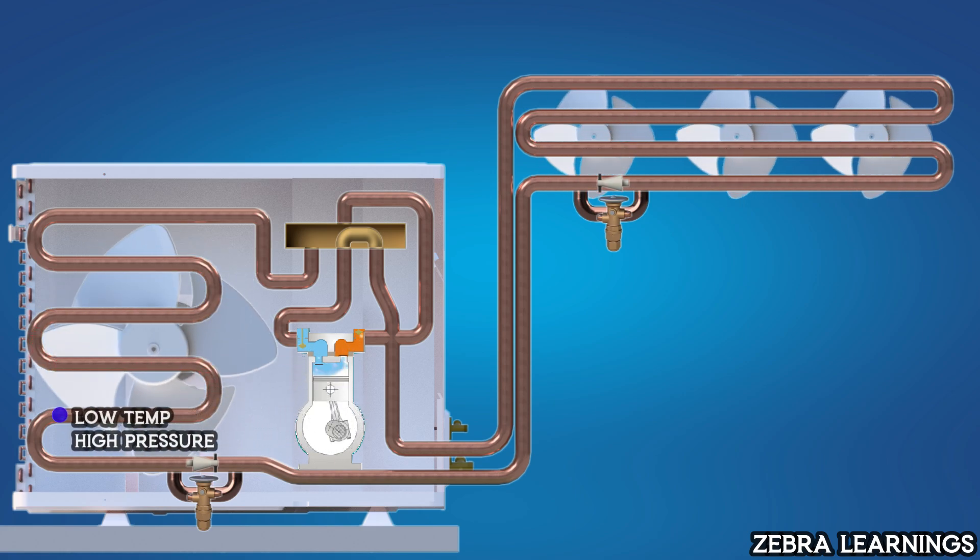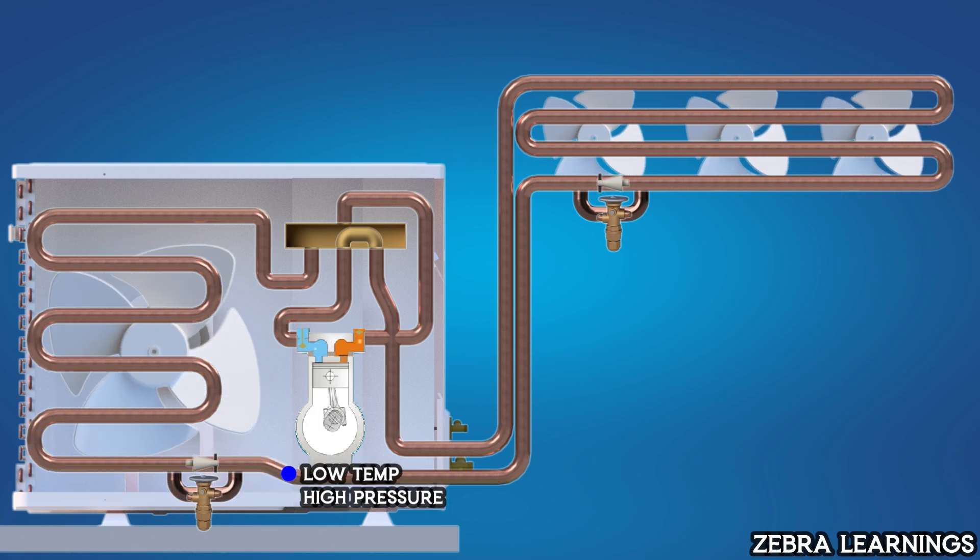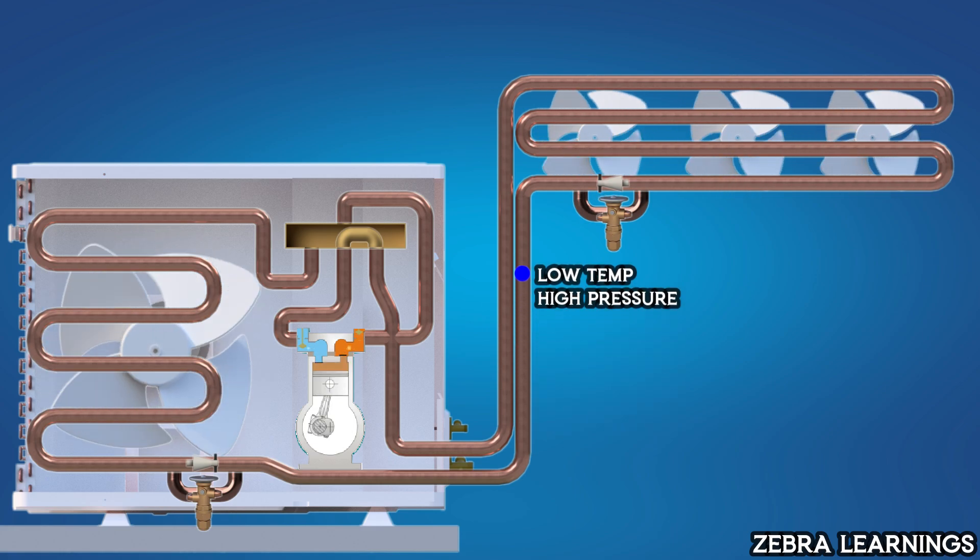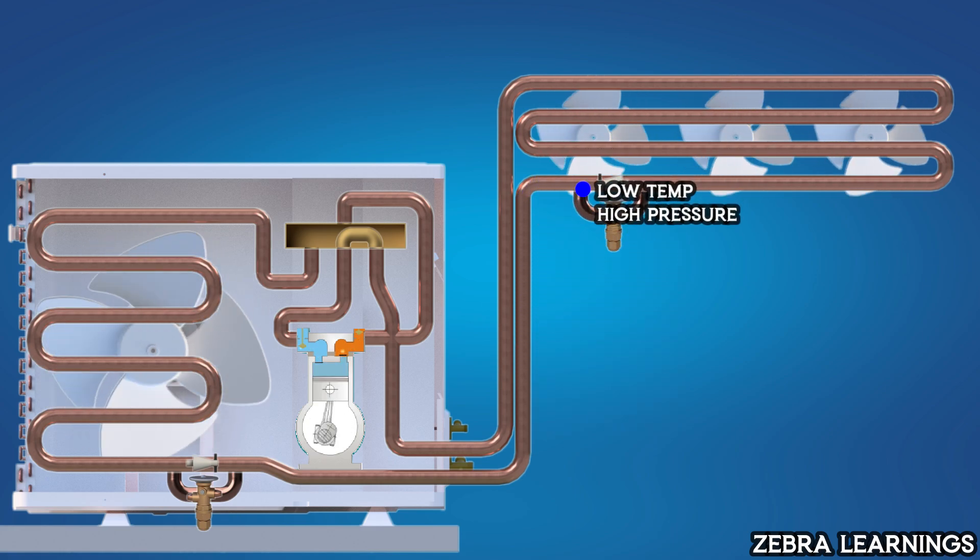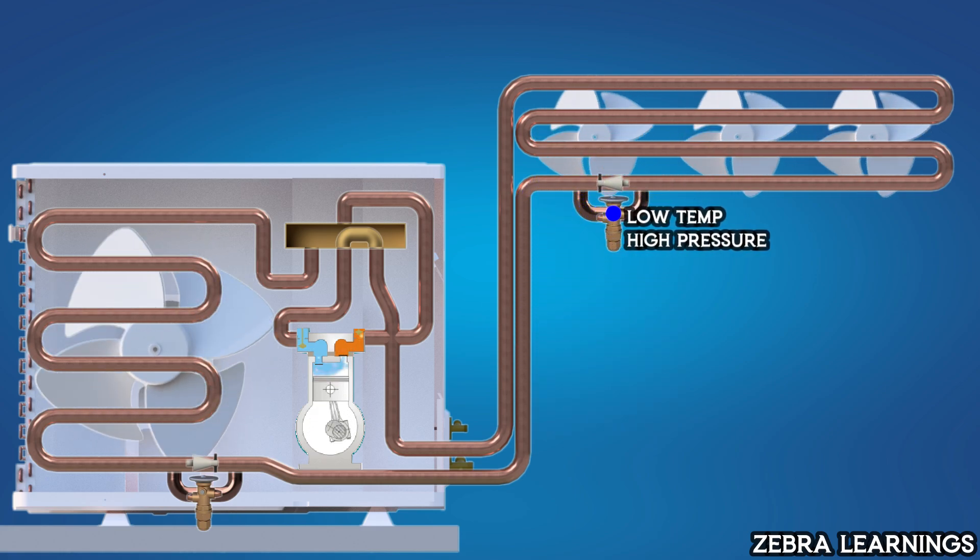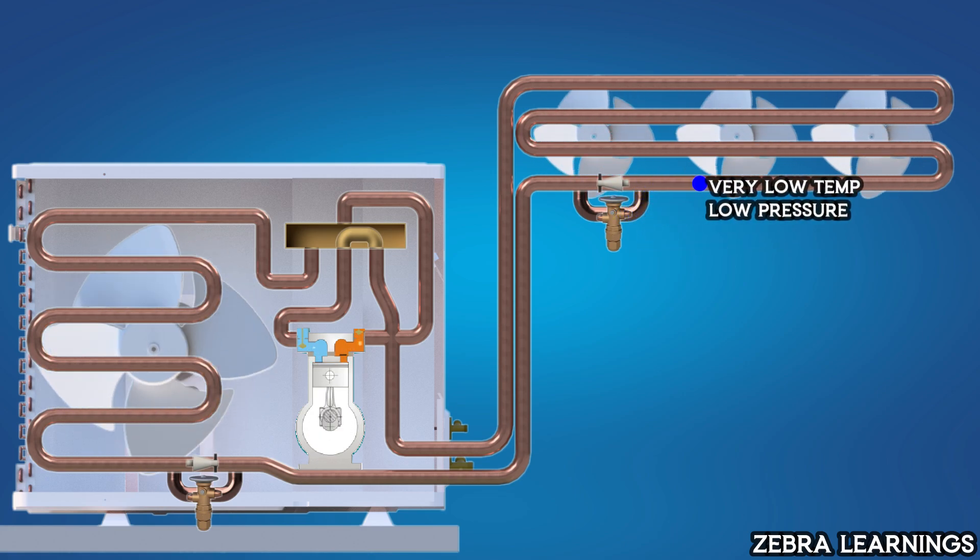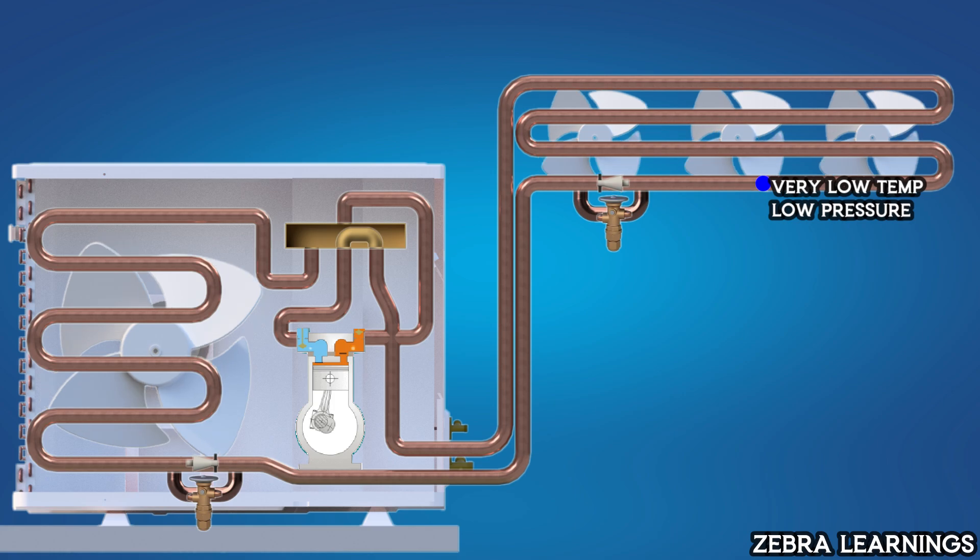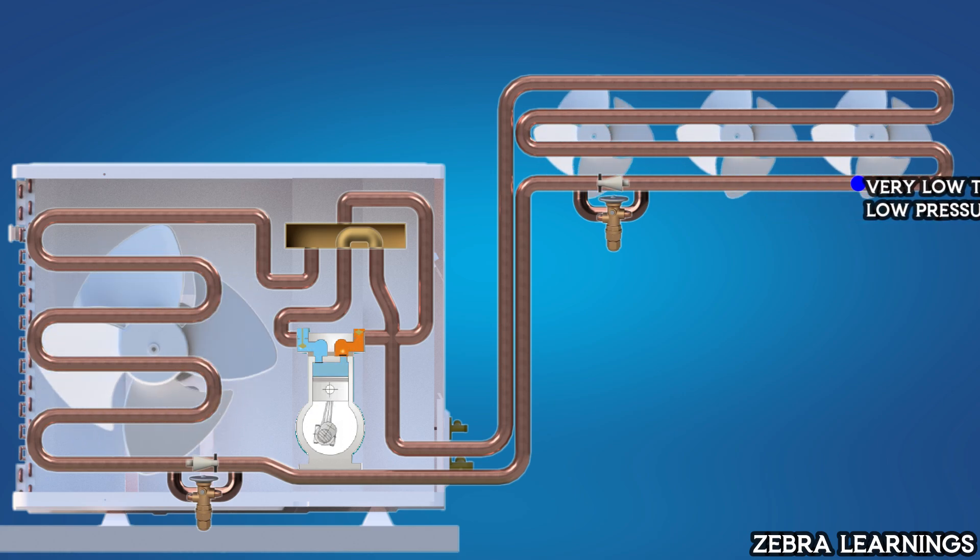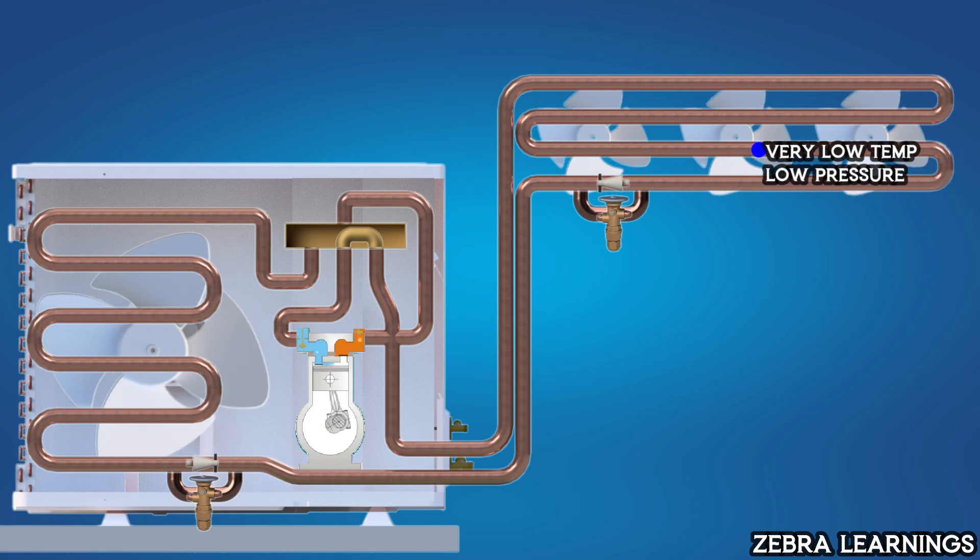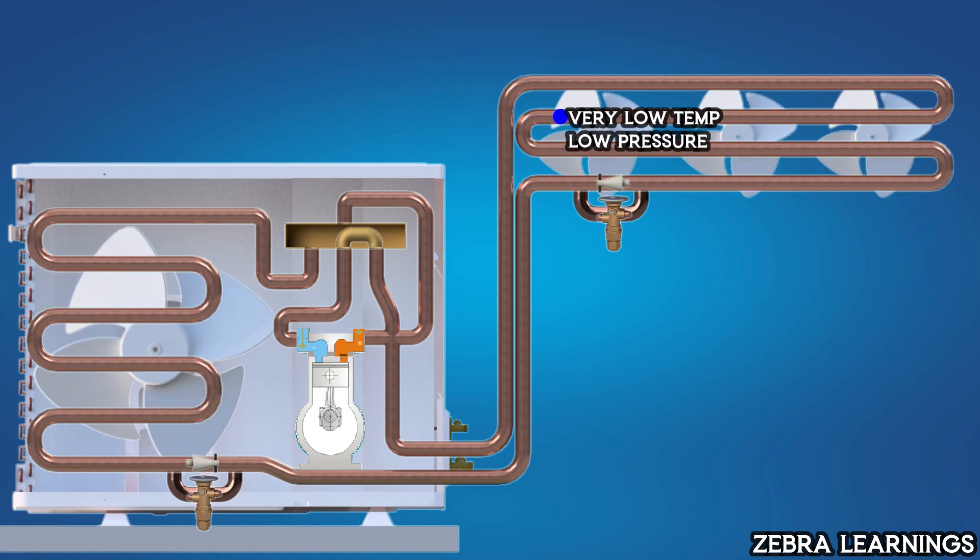In the outdoor unit, the refrigerant cools down and travels through the non-return valve to the indoor unit. Then it passes through the expansion valve. When the refrigerant passes through the expansion valve, its temperature drops significantly, providing a cooling effect as it reaches the indoor coil. The indoor fan motor then blows this cool air into the room.